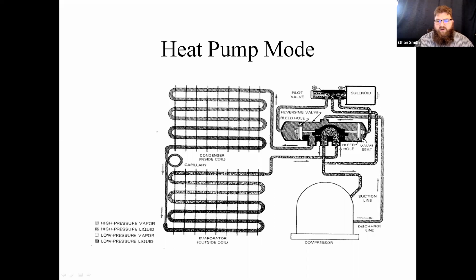Okay, there are some bleed holes in here. It's perfectly normal. We've got to have those, otherwise we'd blow out the valve body at some point. But there are also valve seats here that help limit how much bleed through there is. In the meantime, the high pressure side of the system simply washes over the outside of that clamshell, gets pumped into the condenser, which is now the indoor coil in heating mode, goes through our metering device, goes through the evaporator, which is our outdoor coil now, and we come up through the clamshell and go back into the suction of the compressor.